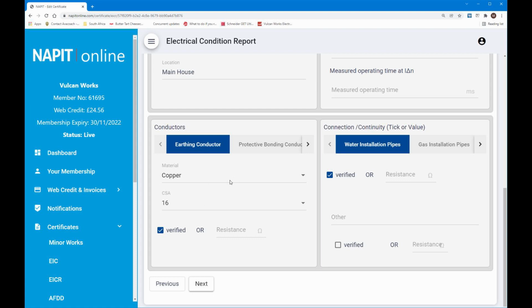Then we come down to the conductors. So the earthing conductors, protective bonding conductors, and the supply conductors, all fine. And like I say, the water installation pipes, they've been verified. That's fine. There is no earthing to the gas or anywhere else. Not needed.